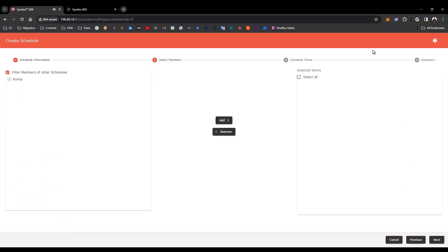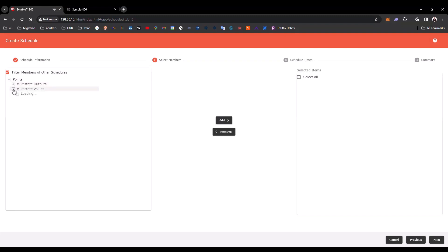Now, in this page, you can select the members of your schedule. Please remember, one member can't be part of two schedules at the same time, for the same period of time. I'm going to select Points, Multi-state Values, and I'm going to select Occupancy Status.